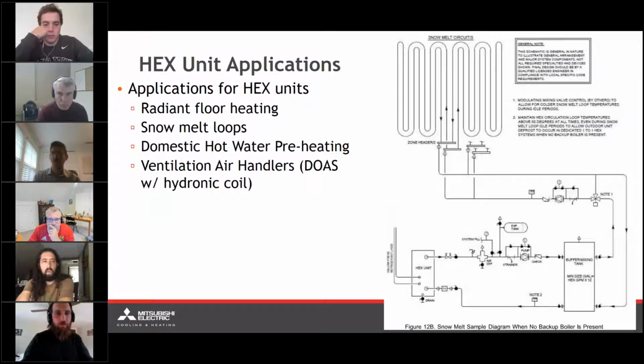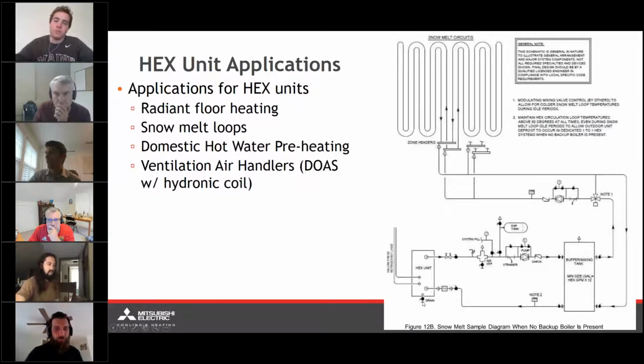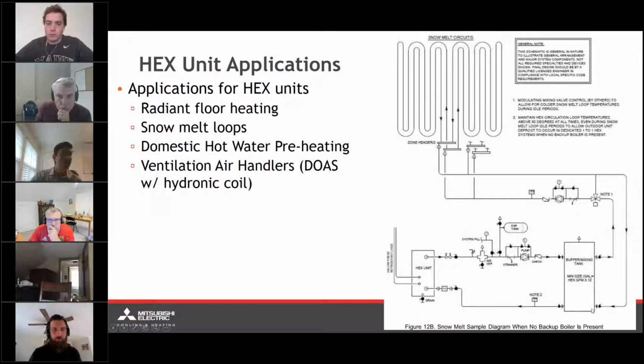So, for this particular schematic, we're looking at a snow melt loop that is entirely driven by an electric heat pump system. Going in, we have the HEX unit in the bottom left here. That's going to be serving the hot water to a buffer tank that's going to be sized for that defrost loop. Again, the minimum size is the GPM rating of the HEX unit multiplied by 12, being the total minutes for the defrost cycle. And downstream of this, we're just going to be delivering that hot water to a zone header and out to a snow melt loop. Ultimately, pretty straightforward.